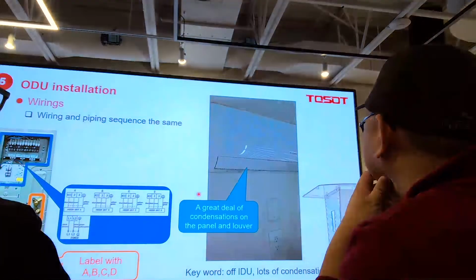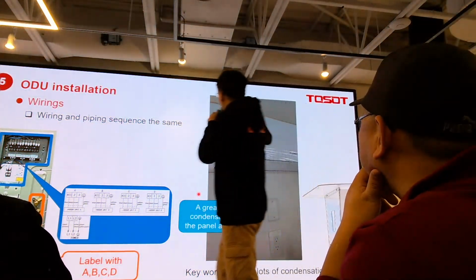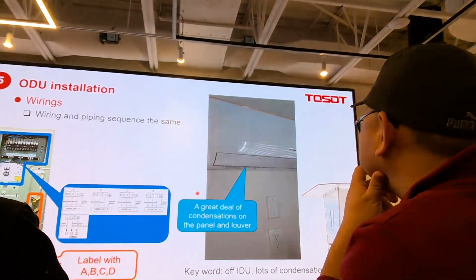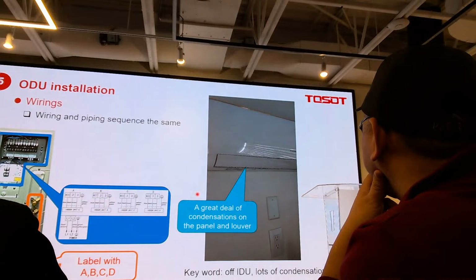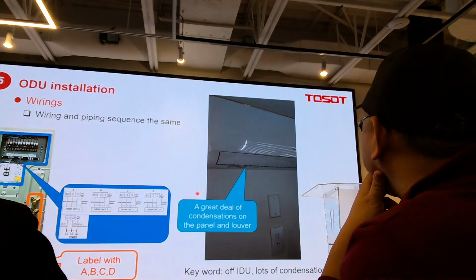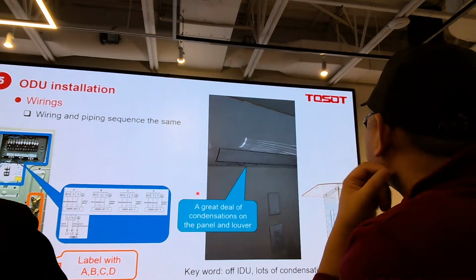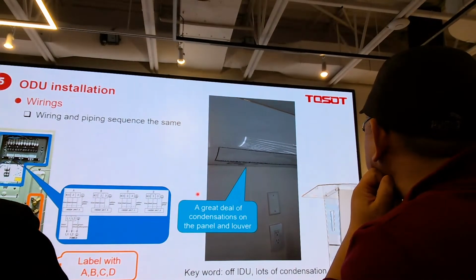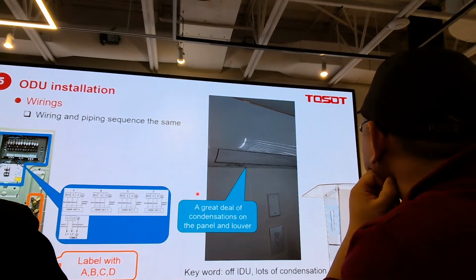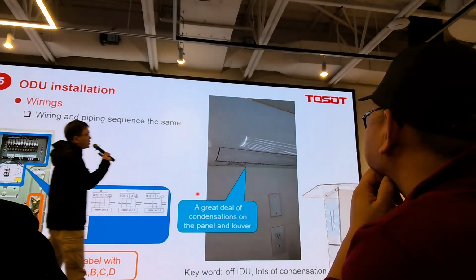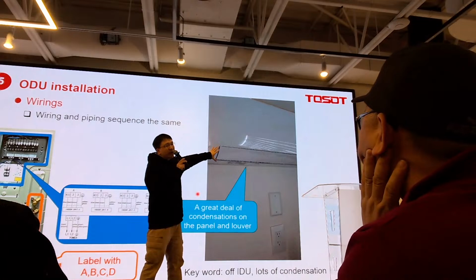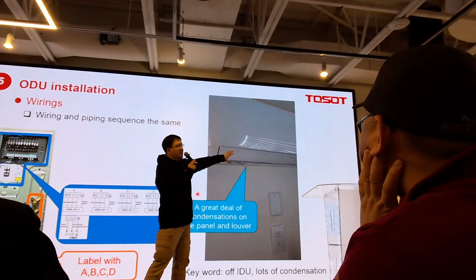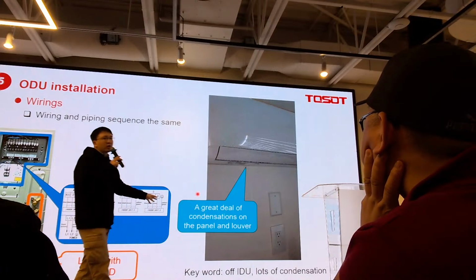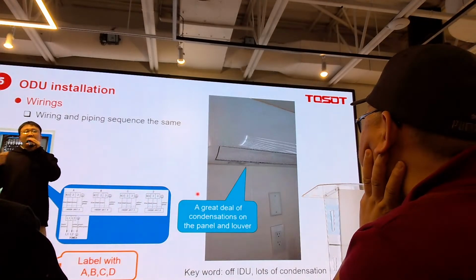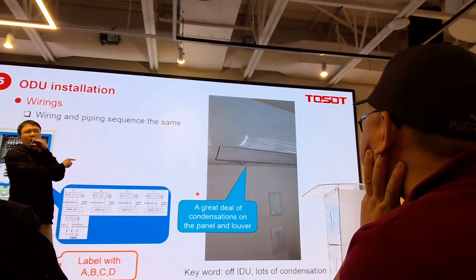Here is another example. If your customer complains like this, watch this video: 'I noticed a major condensation problem with my heat pump in my master bedroom. I hadn't even turned it on, and it was just like this when it was off, with condensation accumulated. Please ask someone to come and check what's going on, get it fixed if possible, and contact me.' So the customer complained that this indoor unit was not turned on, but there was a lot of condensation water. The reason is just due to the wrong sequence. Later I will also show you the diagram of how the refrigerant flow causes this problem.